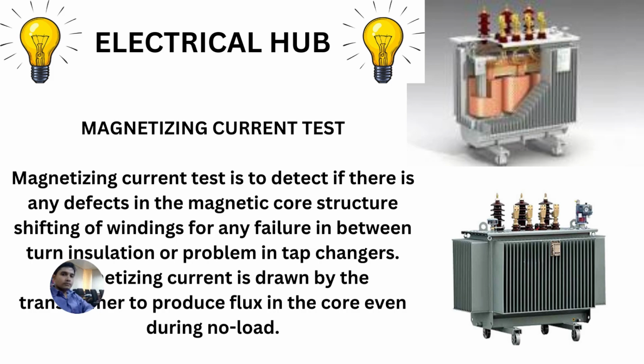It is done to detect if there is any defect in the magnetic core structure, shifting of windings, or if there is any failure in the turn to turn insulation, or if there is a problem in the tap changer. What is magnetizing current actually? The magnetizing current is the current drawn by the transformer to produce the flux in the core even during no load. Means while we just charge the transformer, the magnetizing current produces the flux in the core even during no load.